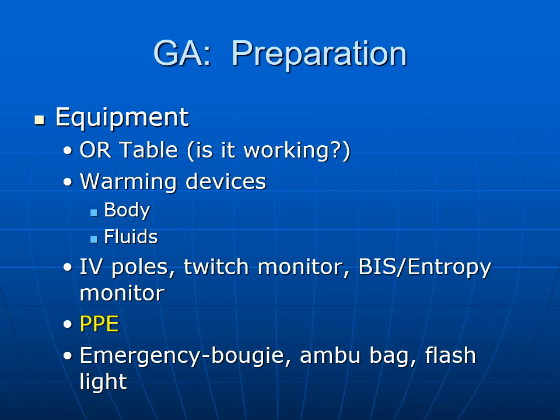All right, IV poles. I cannot tell you, if you're going to do a case where you're going to use muscle relaxant, you need a twitch monitor in there. Now, most rooms are already going to be stocked with it. Make sure it's there. Make sure it works. If they have batteries in there, just because you see it does not mean it's functional. It's your job to make sure before the day starts that that's done.